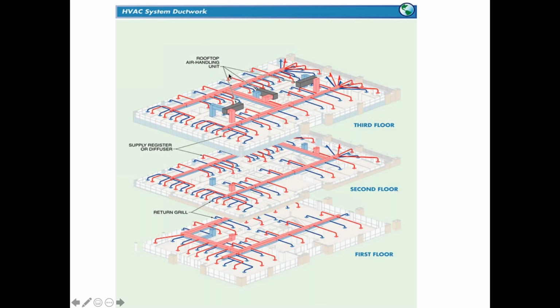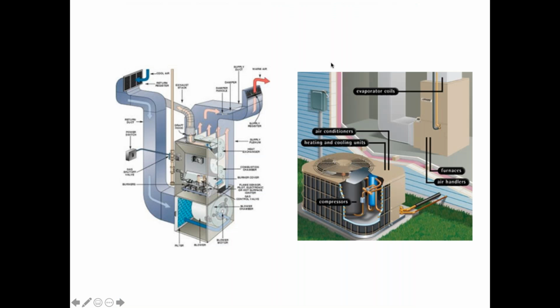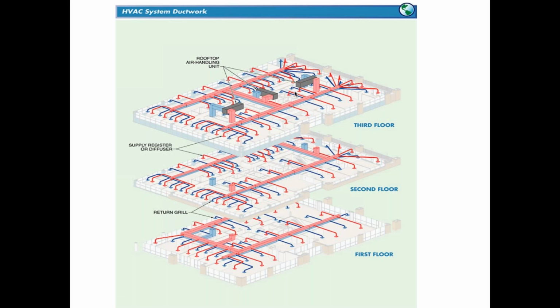Each one of these floors has, in this case, rooftop air handling units. They have ducts that go down and supply air to three floors below it, and from there, air is ducted throughout the three floors and then is returned to the air handling units on the roof. So each air handler there serves one floor. Exactly, it appears that way.